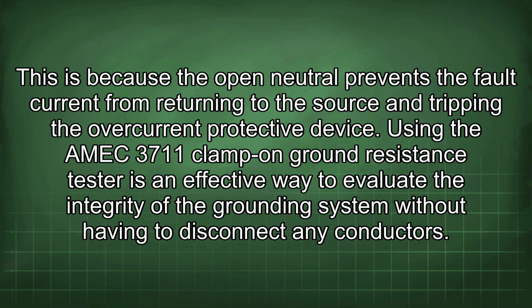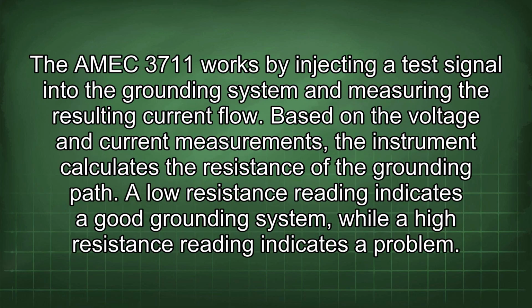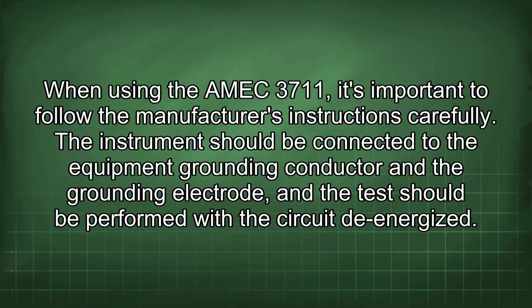Using the AMEC 3711 clamp-on ground resistance tester is an effective way to evaluate the integrity of the grounding system without having to disconnect any conductors. The AMEC 3711 works by injecting a test signal into the grounding system and measuring the resulting current flow. Based on the voltage and current measurements, the instrument calculates the resistance of the grounding path. A low resistance reading indicates a good grounding system, while a high resistance reading indicates a problem.